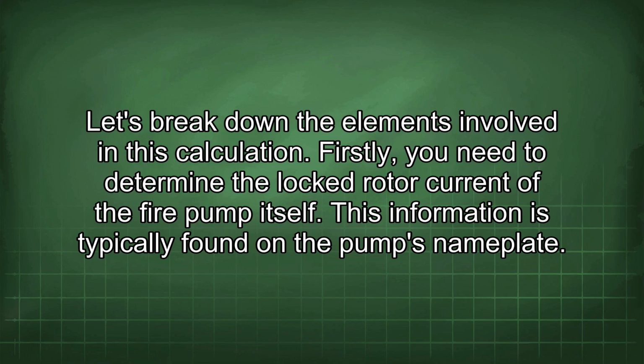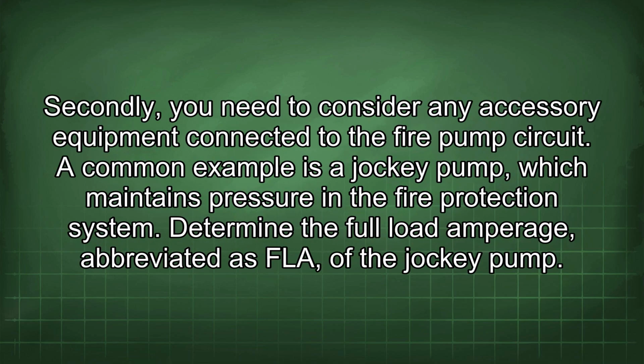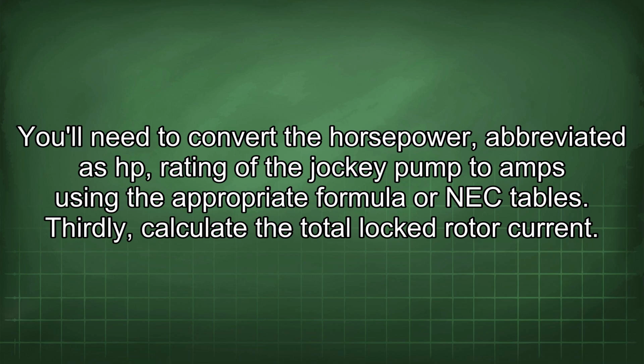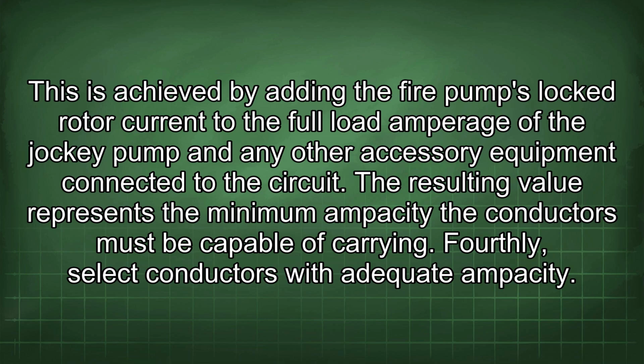Let's break down the elements involved in this calculation. Firstly, you need to determine the locked rotor current of the fire pump itself. This information is typically found on the pump's nameplate. Secondly, you need to consider any accessory equipment connected to the fire pump circuit. A common example is a jockey pump, which maintains pressure in the fire protection system. Determine the full load amperage, abbreviated as FLA, of the jockey pump. You'll need to convert the horsepower, abbreviated as HP, rating of the jockey pump to amps using the appropriate formula or NEC tables. Thirdly, calculate the total locked rotor current. This is achieved by adding the fire pump's locked rotor current to the full load amperage of the jockey pump and any other accessory equipment connected to the circuit. The resulting value represents the minimum ampacity the conductors must be capable of carrying.